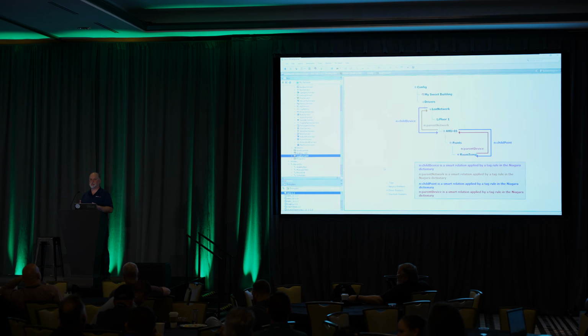Now, if you want to apply a Haystack data model, Brick data model, things like that, yes, there's more effort involved. But I'll also be the first person to say you don't need to data model everything in the application either. I think you need to think about critical things like, what do I want to display in a graphic, or what do I want to be able to do fault detection on. And if you are going to go down that route of using Haystack or Brick, you do want to learn about that ontology and try to apply it in a standard way that other people who encounter your data would understand.